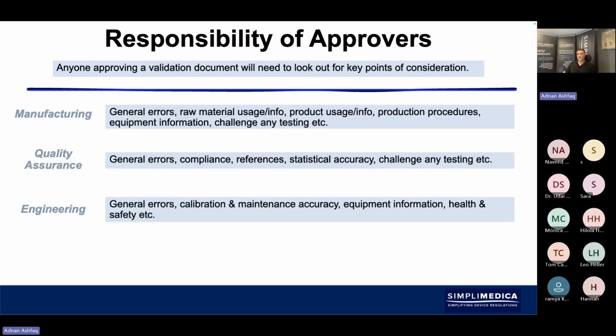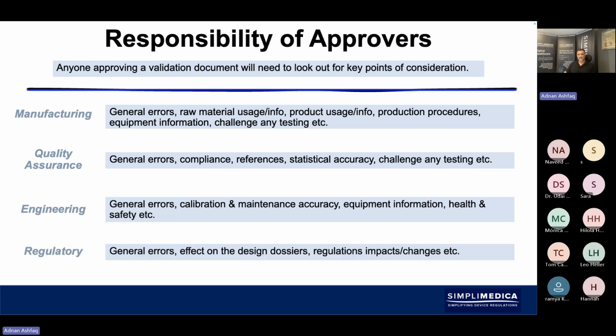So, responsibilities of approvers. When manufacturing are approving documentation, they should be looking at general errors for raw material usage, product usage, whether production procedures have been quoted correctly, and whether equipment information has been documented, and also challenge any testing. Quality assurance, when signing off documentation, should be looking for general errors, compliance, references, statistical accuracy, and also challenge any testing. Engineering, if they're signing off, should also be looking for general errors, but also for calibration and maintenance accuracy, equipment information, health and safety, etc. There could be some other things. And regulatory may also sign off for general errors or for effects on design dossiers, regulation impacts and changes.